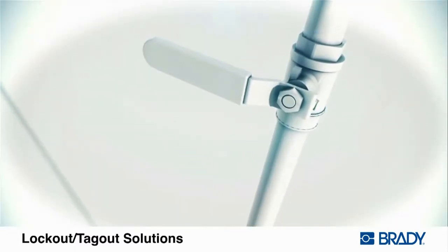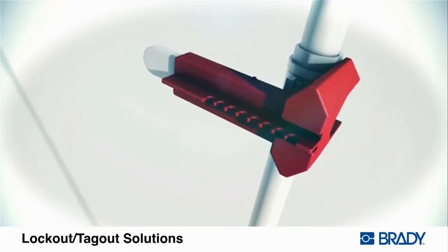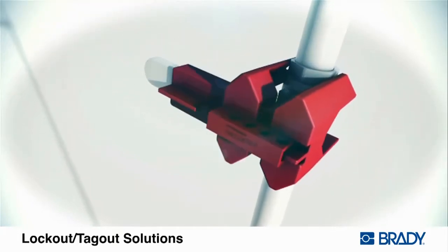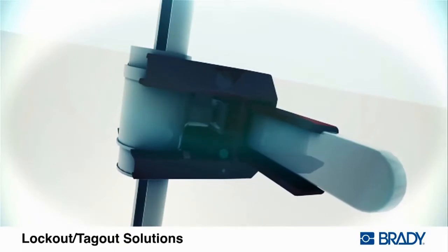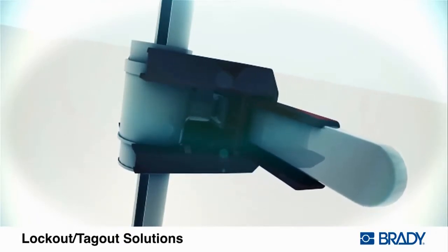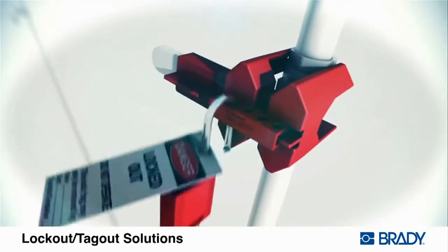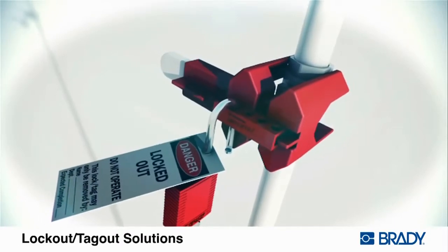Place the base of the lockout over the ball valve handle. Then, slide the mating attachment over the end. Make sure the handle is captured in the cavity of the mating attachment. Finally, insert the lock through the hole that provides the tightest fit.